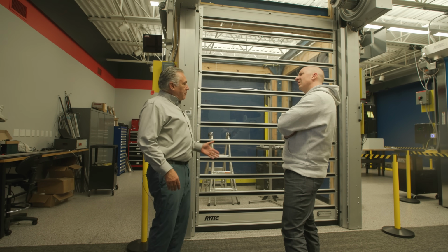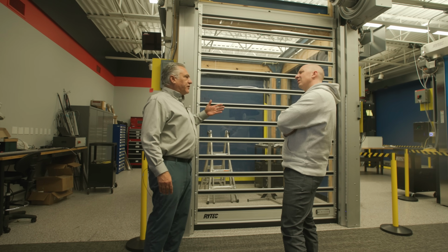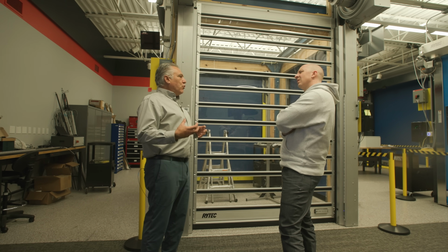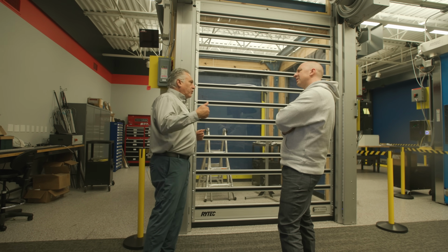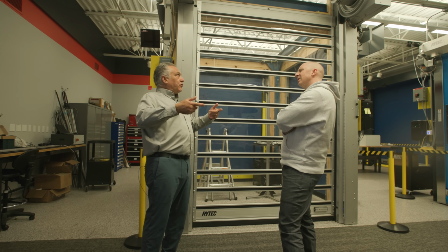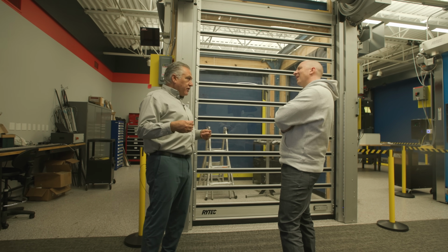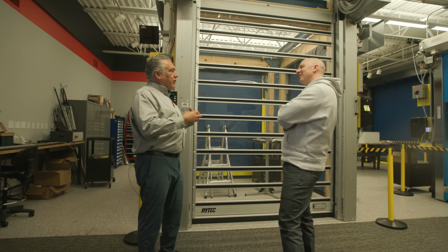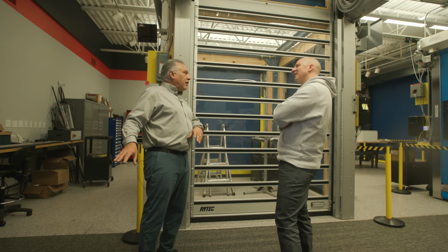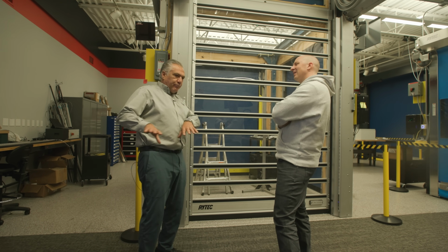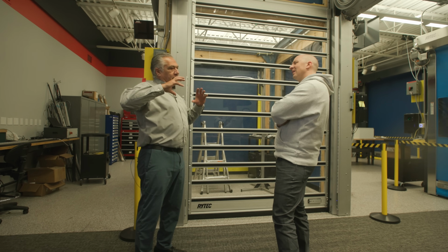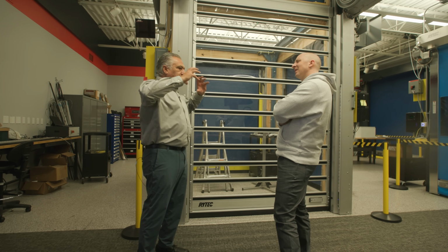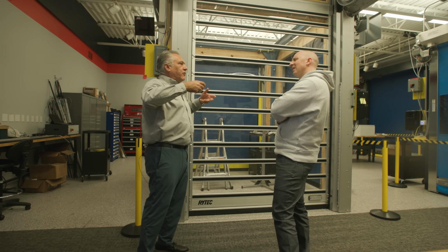So we have that capability, and when you drive a door to accelerate it, it's under load. And when you go to slow a door down or stop it, it actually turns the motor into a generator. And then that generated power comes back to the controller and gets burned off like a toaster. We just burn it off. In that sense, we're controlling the door movement by saying, okay, slow down.